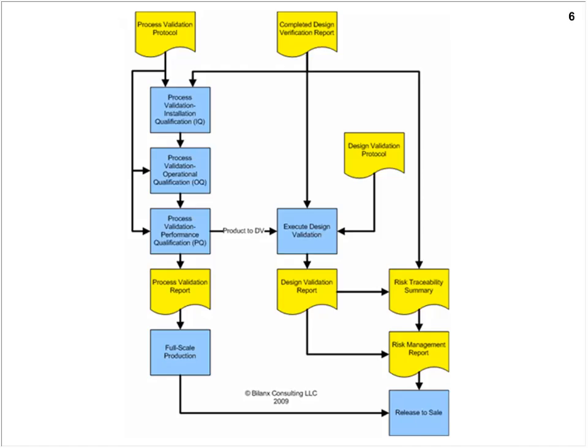This is one area that I've found sometimes in doing audits that people have written their validation report and gone ahead and moved into the actual full-scale production, when if you go read the validation report in either the process validation or the design validation, you'll find, in fact, that you did not meet the requirements in the protocol. And, of course, this is a case for a violation of the FDA regulations, is putting product on the market that does not meet requirements, that is adulterated then, and you would be cited for that and susceptible to a warning letter.